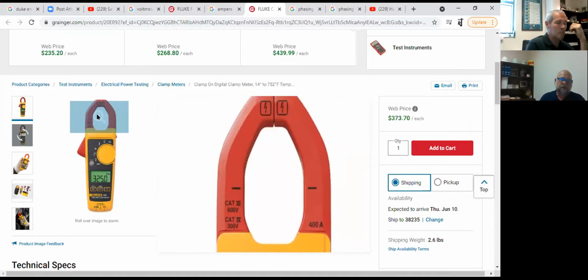It's a very good tool to use, especially if say you have a customer out there that wants a service disconnected out of a transformer, and there's 5 or 6 services in there and there's no current, you've pulled a meter on that service. There's nothing going to it, no flow going to it. You can take the amp meter and start clamping around your conductors one at a time. The one that has no flow, that you know has no flow, will most likely, 99% of the time, be the conductor you want to disconnect for. Yeah, so it's a good piece of equipment.